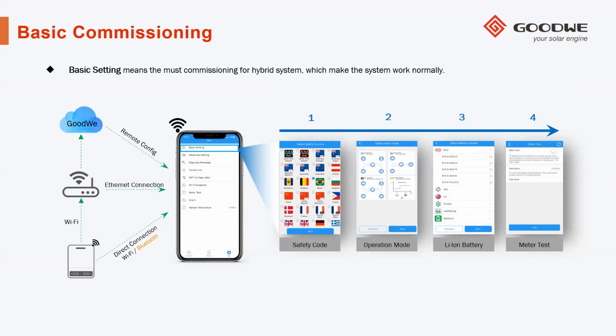The lithium-ion battery options available on the application are entirely dependent on the inverter's firmware. So when we update our list of compatible batteries, with the BYD, LVLs and all of that, which will be on our app soon, there will be a new update for the inverters, which will then accommodate all of those selections. The meter test tests the communication between the batteries as well as your energy meter. When that test is run, you'll have to ensure that at least 150 watts is being drawn from the grid so that the CT can accurately detect the current flowing.